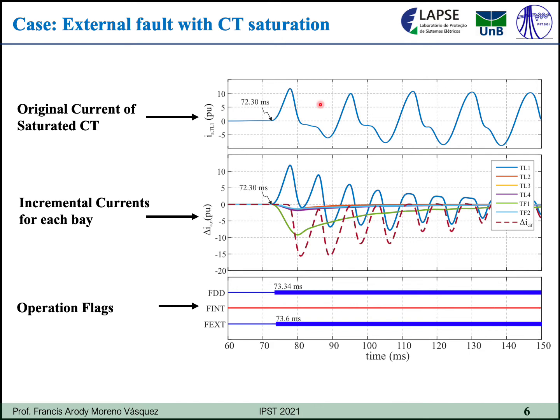Now we have an external fault which causes a high degree of saturation of the CT, and the external fault occurs at feeder TL1, the blue line here. It can be noticed that the polarity of this incremental current is opposite to the incremental current of the rest of the feeders, as well as to the incremental differential current. In this case, the external fault is identified.